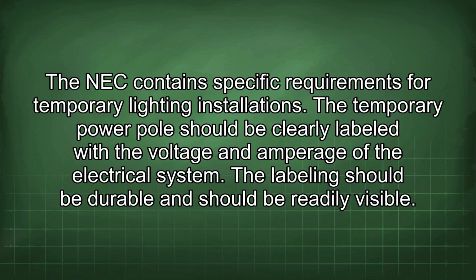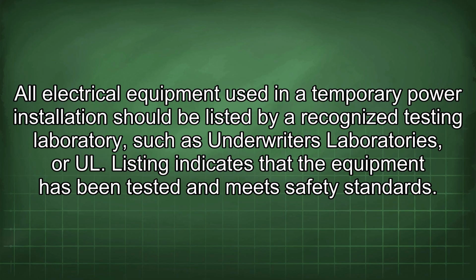The temporary power pole should be clearly labeled with the voltage and amperage of the electrical system. The labeling should be durable and should be readily visible. All electrical equipment used in a temporary power installation should be listed by a recognized testing laboratory, such as Underwriters Laboratories, or UL. Listing indicates that the equipment has been tested and meets safety standards.